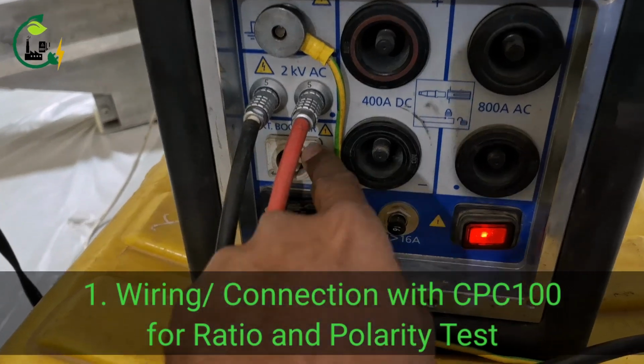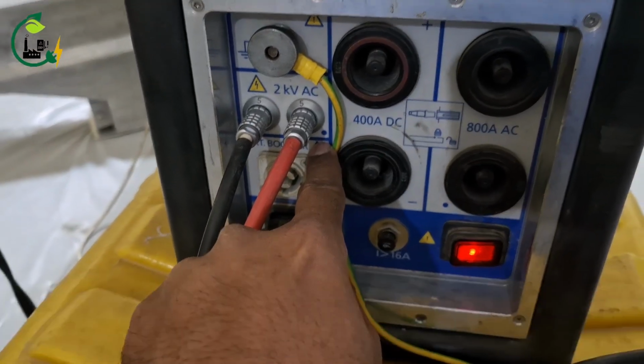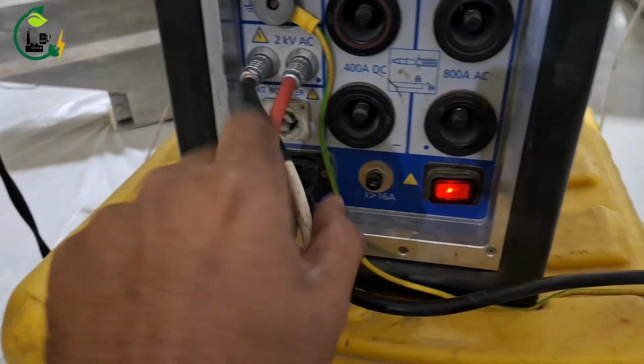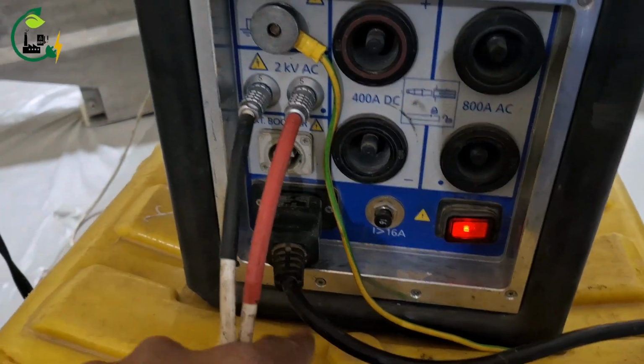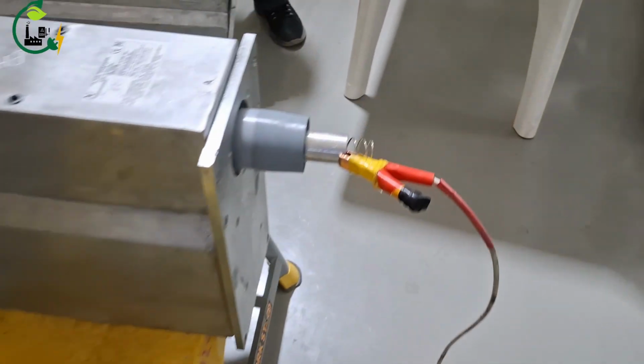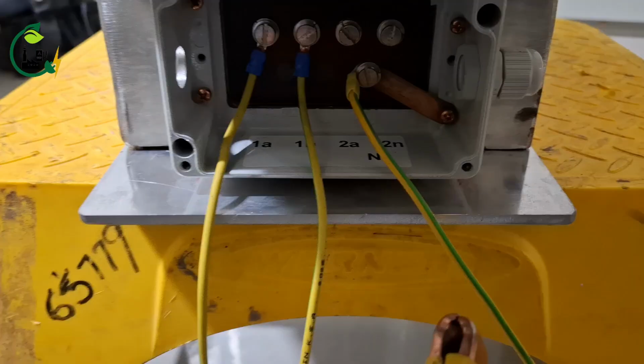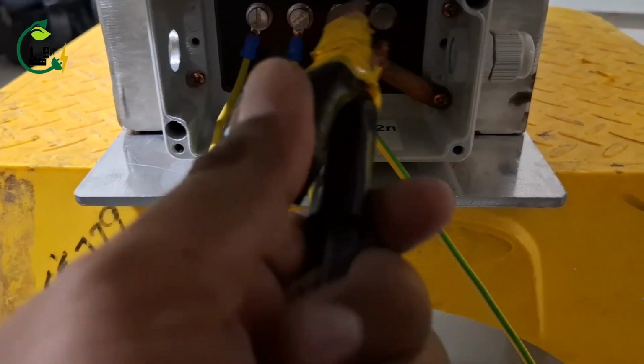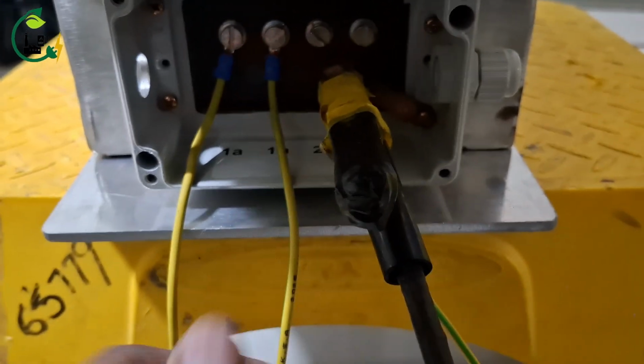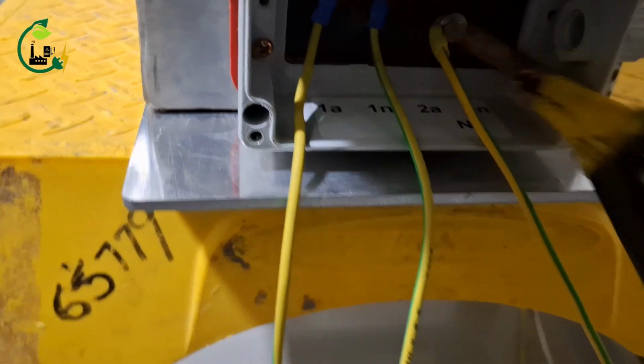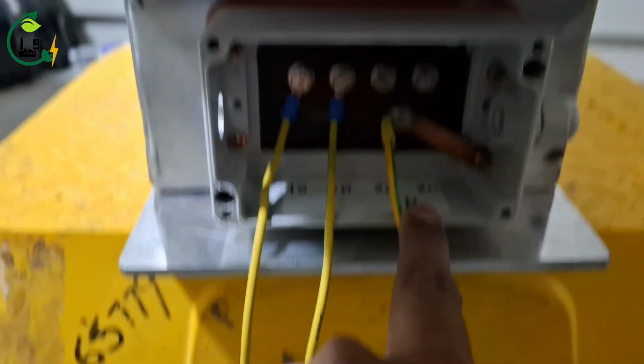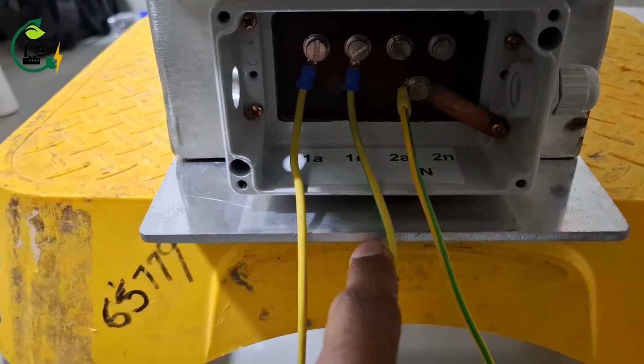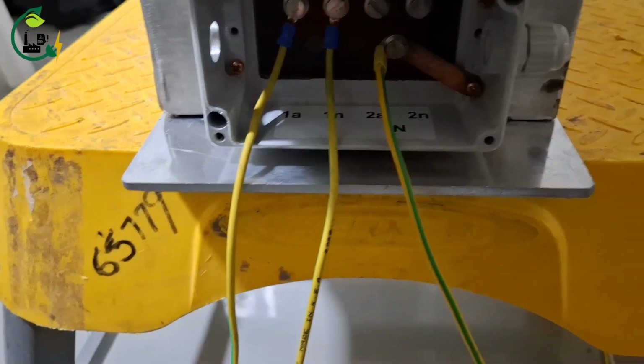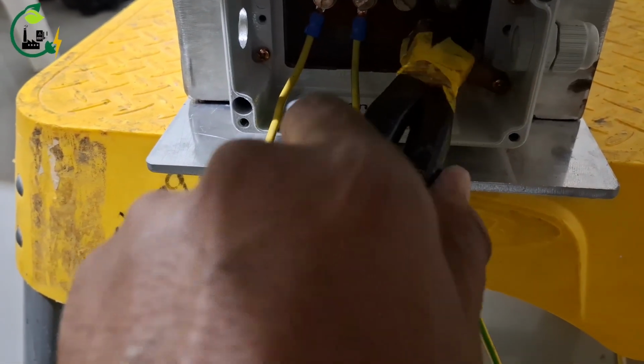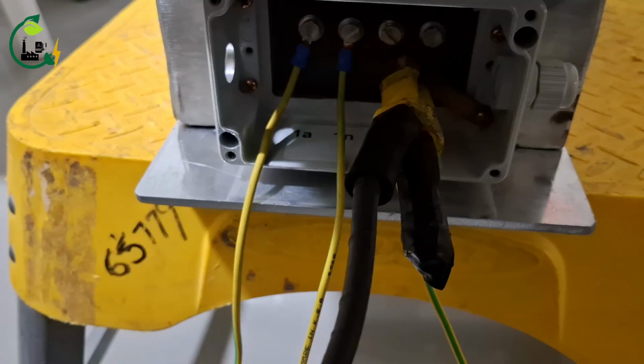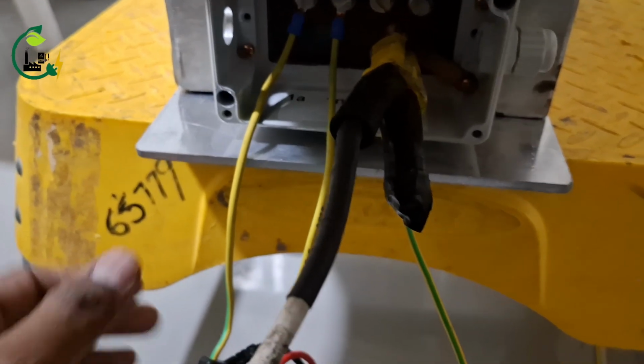These are the primary connections, 2 kV AC. Here is the dot point, so I connected red, that is P primary, capital A, with the dot. This is the main point which connects with the bus bar, and the black wire I will connect to capital N for VT ratio testing and polarity testing. Make sure to follow the dot point, otherwise the polarity will not be confirmed. So check your drawing to check the polarity.